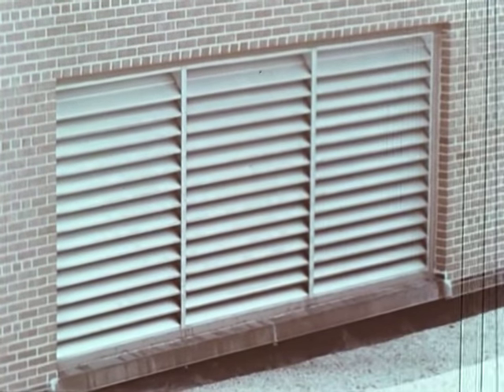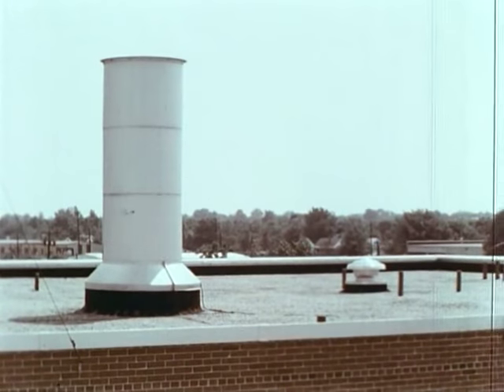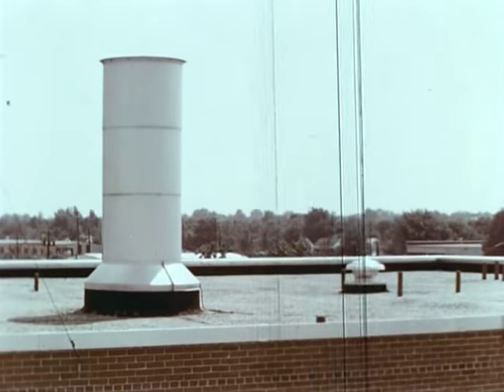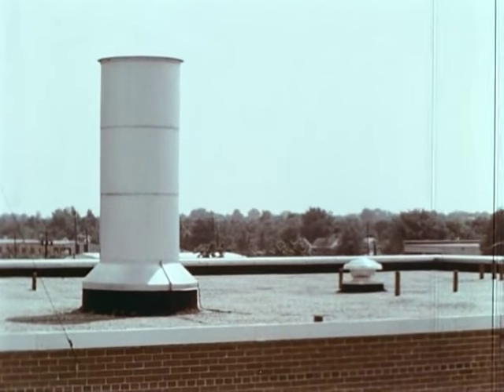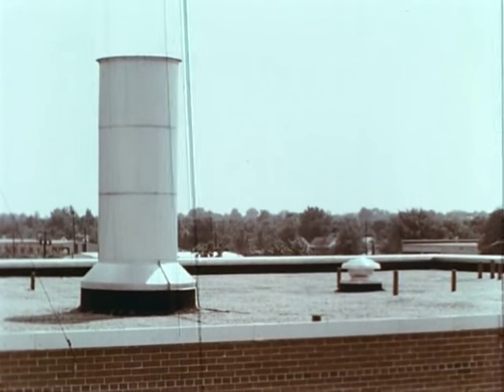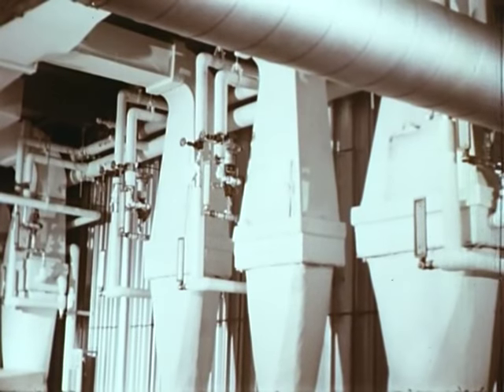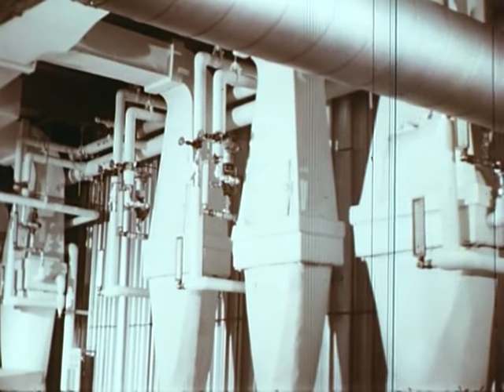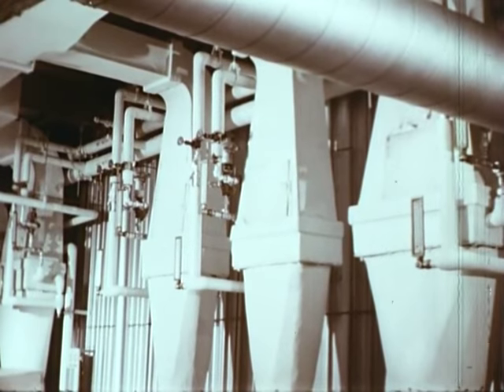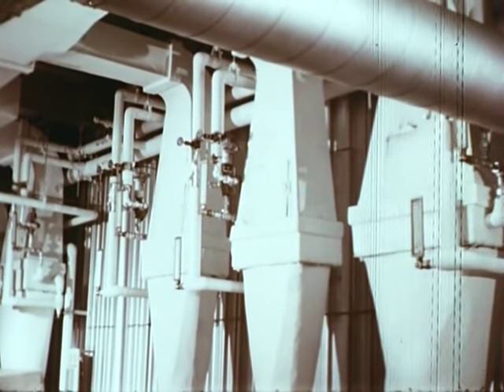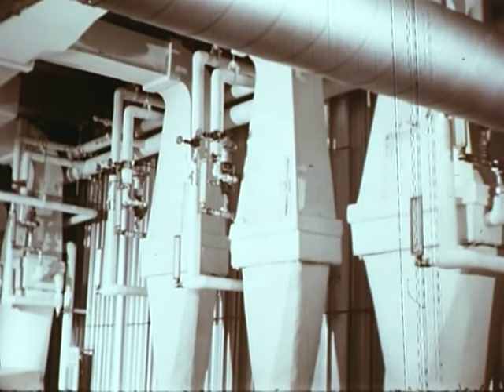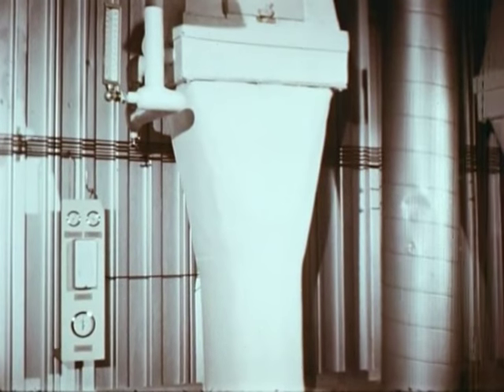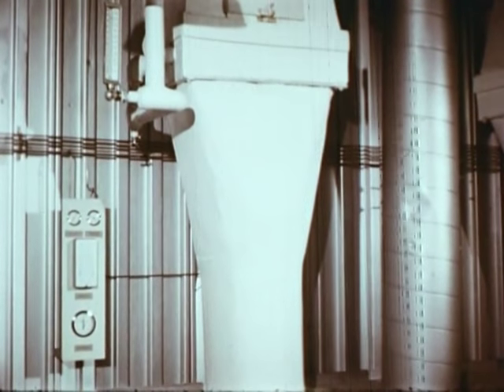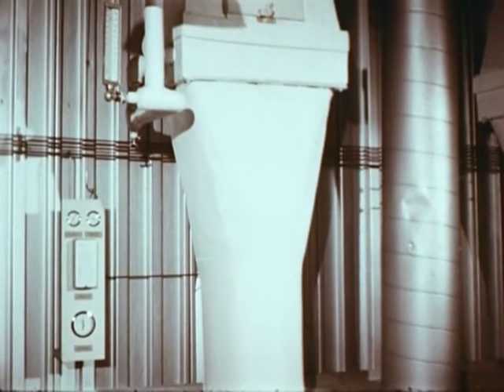One vital consideration is the need to locate the air intake grill upwind to the exhaust stack. There should be adequate physical separation between both to prevent cross-contamination. In engineering support, air ducts going to each room in the infectious zone should deliver non-recirculating, filtered, and conditioned air. In virus labs, inlet air is often passed through ultra-high efficiency filters. These ducts need to be of airtight construction.